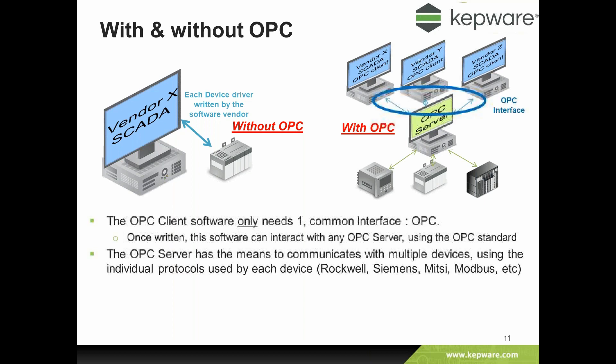Without OPC, the driver and the software consuming the data are in one package and must be written by one vendor. With OPC, you have a completely different topology: OPC client applications only have to write one interface — the OPC interface — and then they have access to data from lots of different types of devices. They don't have to continually write new drivers as new equipment gets launched onto the market.